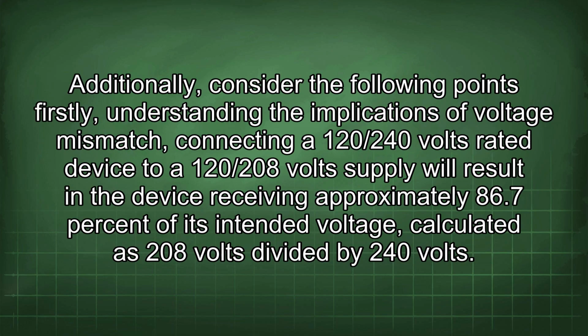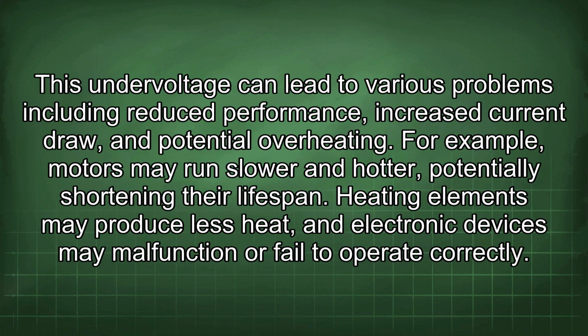Additionally, consider the following points. Firstly, understanding the implications of voltage mismatch. Connecting a 120/240 volts rated device to a 120/208 volts supply will result in the device receiving approximately 86.7% of its intended voltage, calculated as 208 volts divided by 240 volts. This undervoltage can lead to various problems, including reduced performance, increased current draw, and potential overheating.